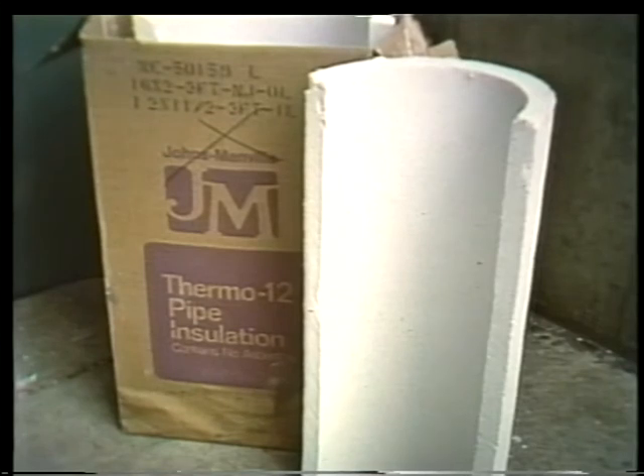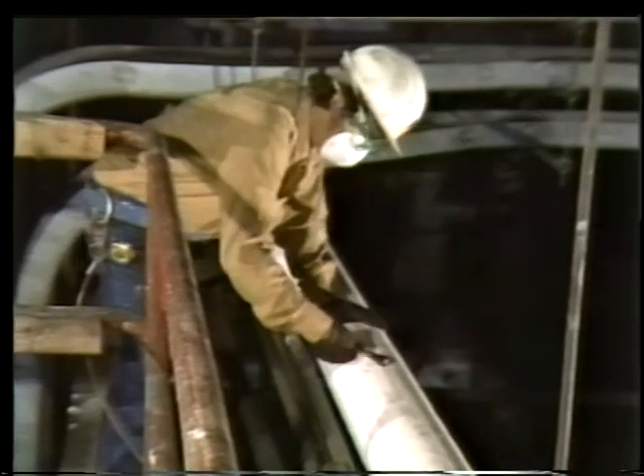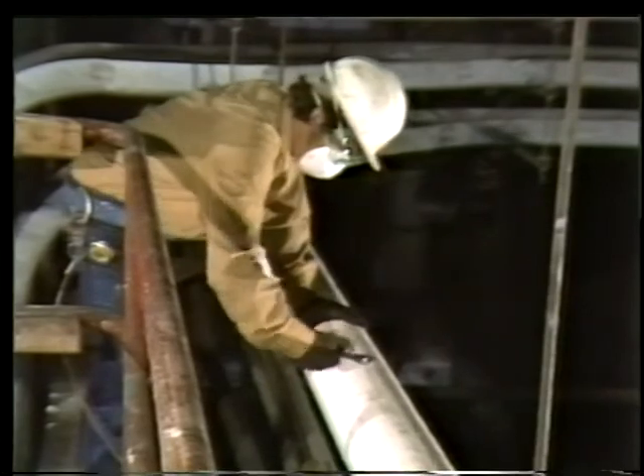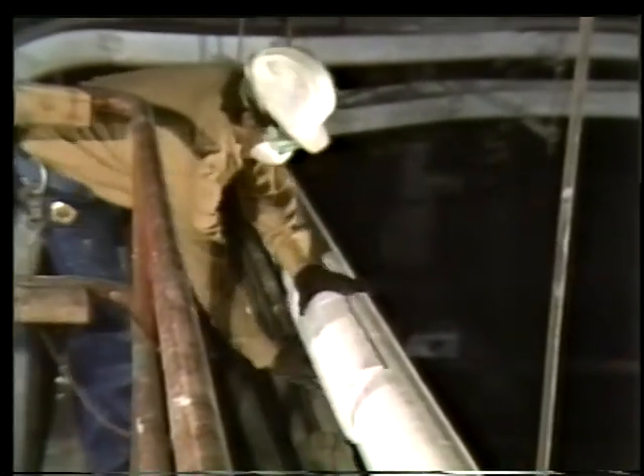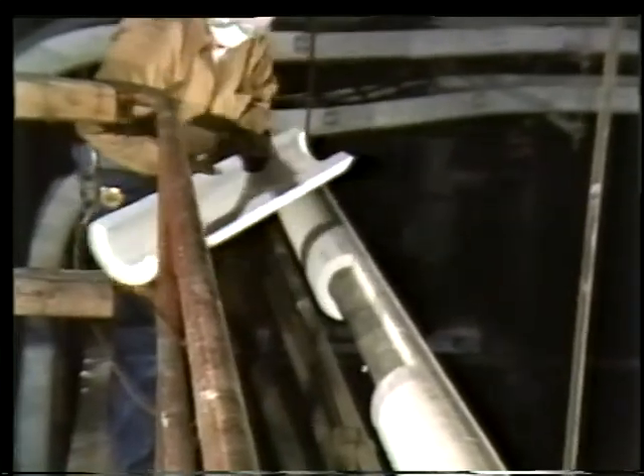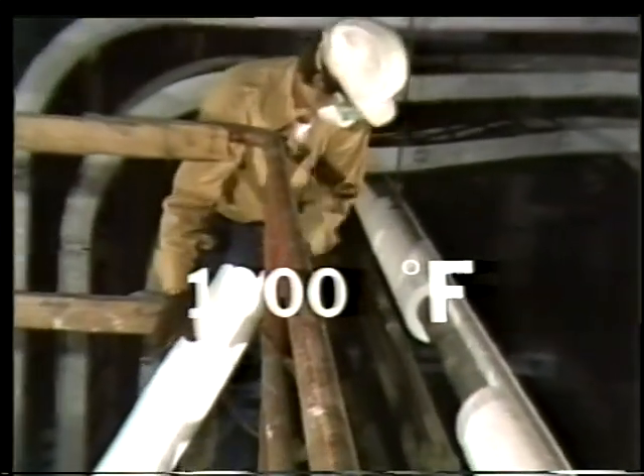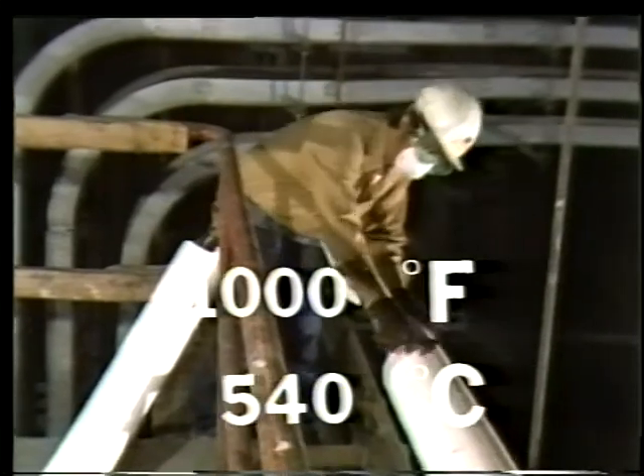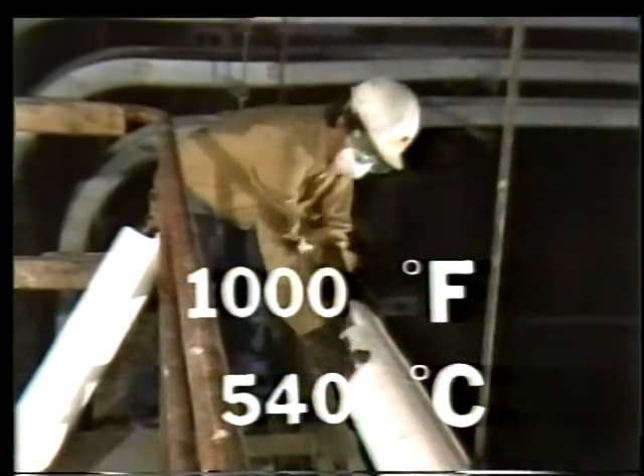Calcium silicate is molded mass-type insulation. It combines lightweight with considerable strength. You'll see it used most often on high-temperature piping, like steam lines, because calcium silicate is high-temperature insulation. It can withstand temperatures of up to 1,000 degrees Fahrenheit or 540 degrees Celsius without burning or melting.